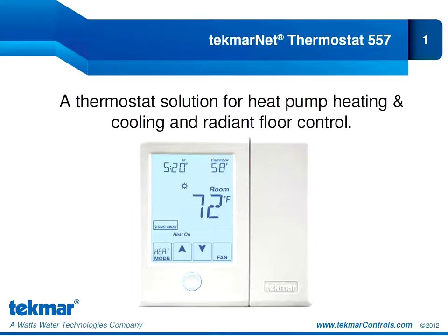The 557 introduces Tekmar's thermostat solution for radiant heating and cooling with heat pumps. It is the only thermostat on the market designed to operate a one- or a two-stage water-to-air or air-to-air heat pump together with a radiant floor. Also, depending on your application, we can support up to 4 stages of heating, 2 stages of cooling with fan control and with humidity control.